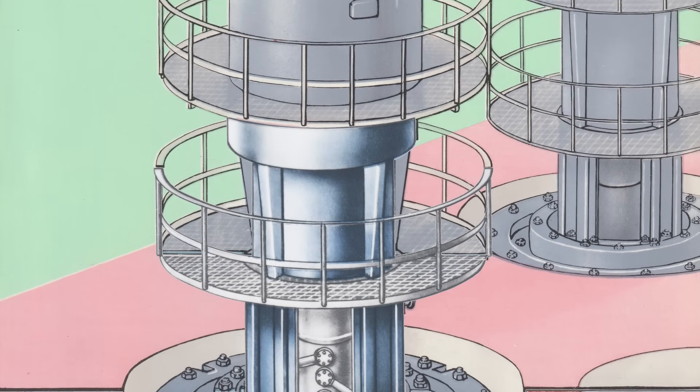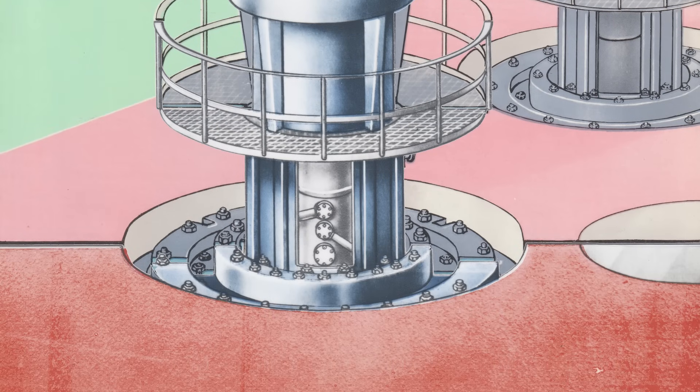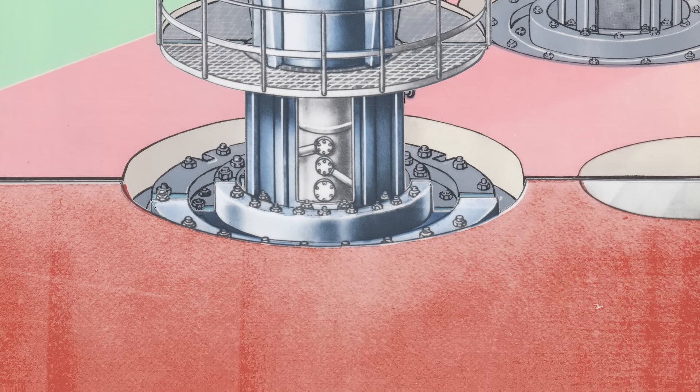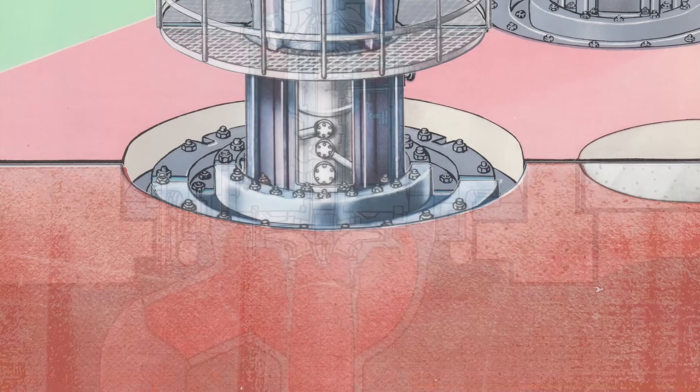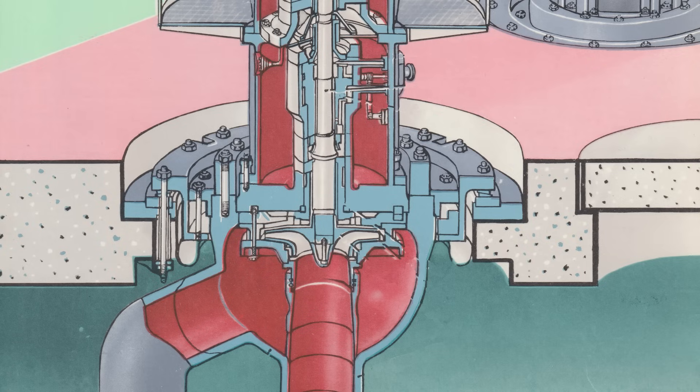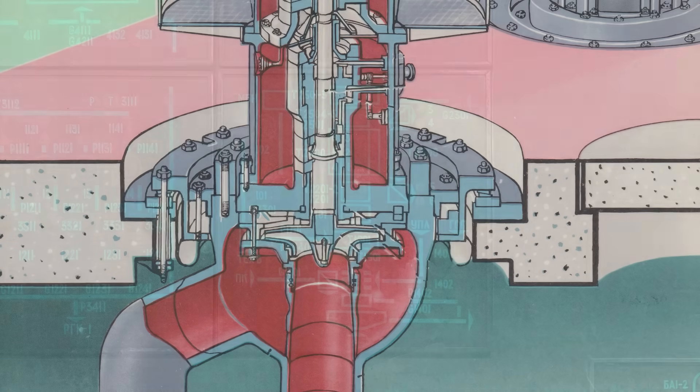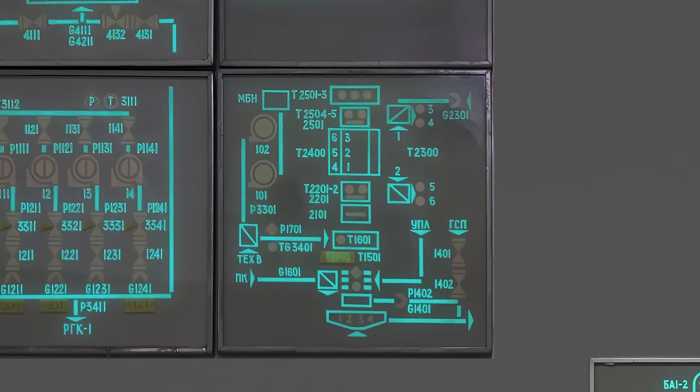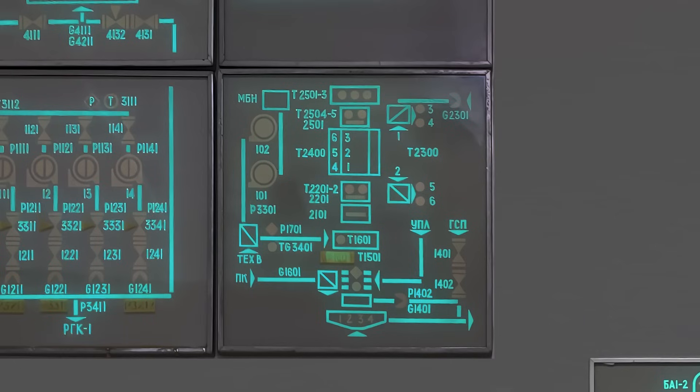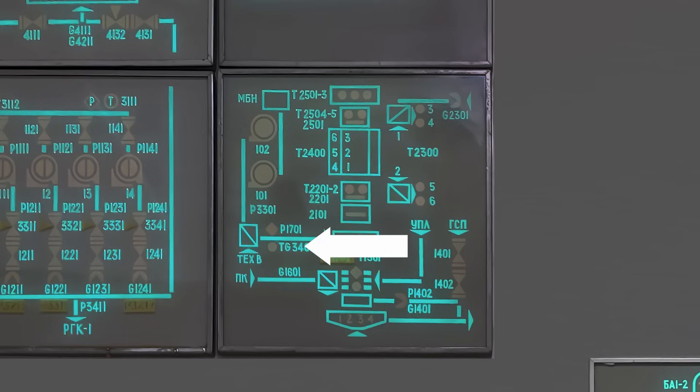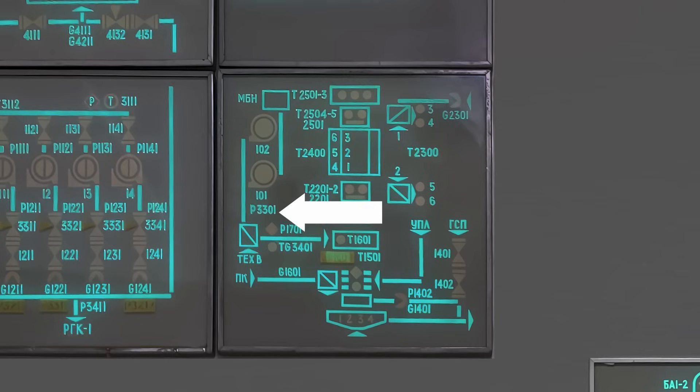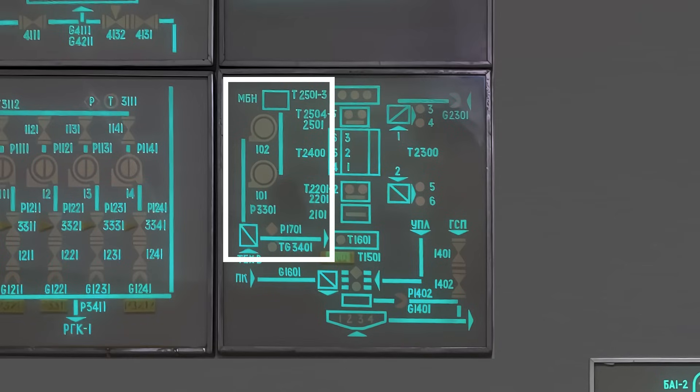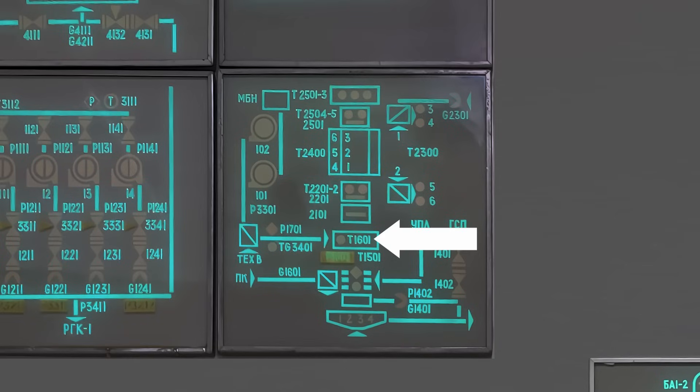Well, here you may recall from our previous episodes how massive these pumps are and to operate properly they rely on several support systems, which you can see on this display. Look closely, do you see it? The shape actually resembles the pump, which exactly that is indicated by these digits. So there are many many sensors that monitor each part of the pump to catch any problems early and, well, there are points to monitor. For example, this is the lubrication system. It has a smaller pump to deliver filtered oil to the pump's bearings. As they rotate at a really crazy speed, the oil gets hot, so it is cooled by technical water in special exchanger.